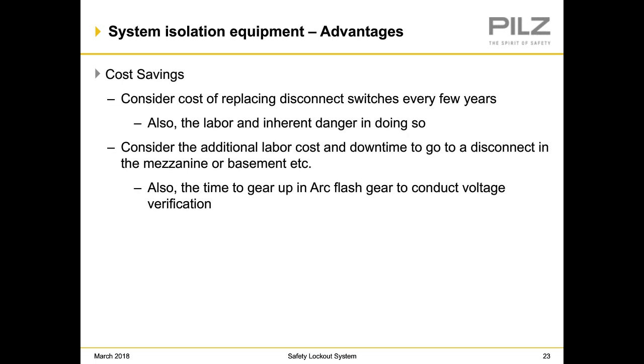As well, another advantage of system isolation equipment is cost savings. So, if you consider the cost of replacing disconnect switches every few years in a frequent use application, also the labor and inherent danger in replacing those switches, also if you consider the additional labor cost and downtime to go to a disconnect that might be located way up in a mezzanine or down in a basement, and the time needed to gear up and put the arc flash gear on to conduct the voltage verification, all those go away with the use of a system isolation equipment.